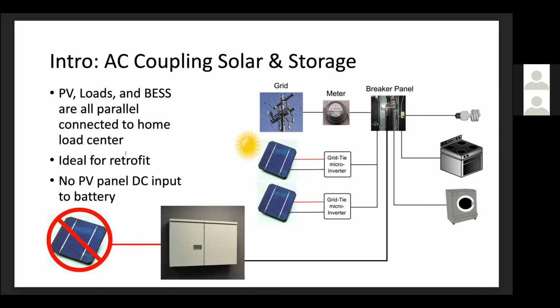This is ideal for the retrofit market. And please note that there is no PV panel or PV module DC input to the battery system itself. All PV modules must have their own PV inverters, be they micro inverters or string inverters, doesn't really matter. Conceptually, that's all connected in parallel. But you'll see in the coming slides where the interconnections are and how they are managed.